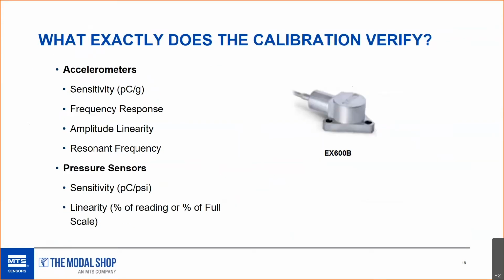So what does the calibration verify? What kind of data are we taking? It varies a little bit here. Common ones are the sensitivity for an accelerometer, the frequency response, the amplitude linearity, the mounted resonant frequency of the accelerometer. Pressure sensors, same thing, sensitivity, linearity.